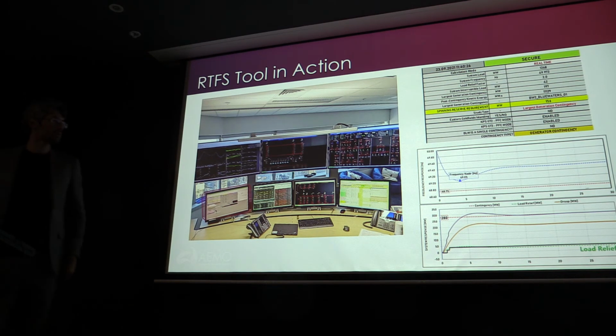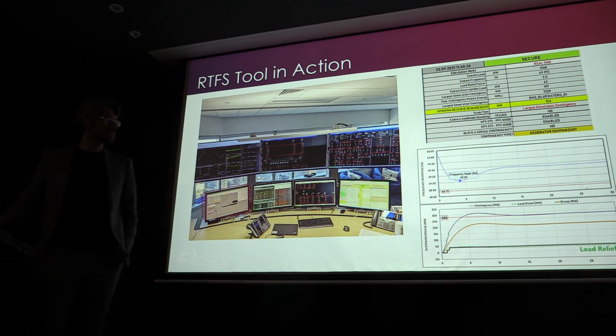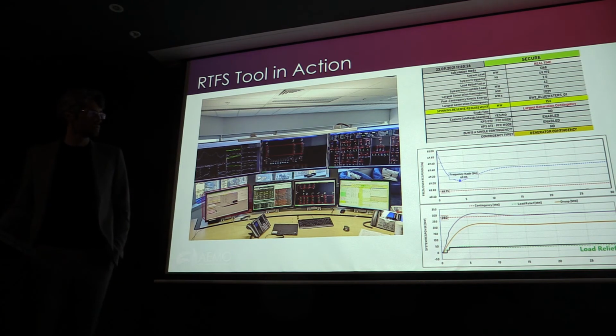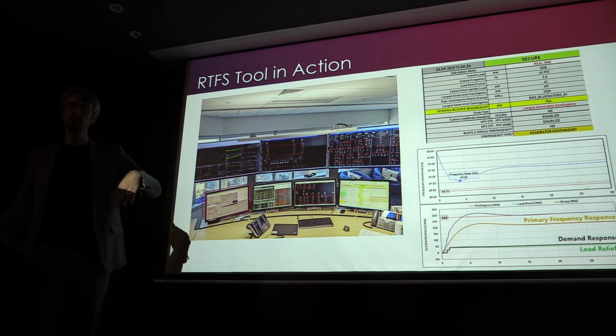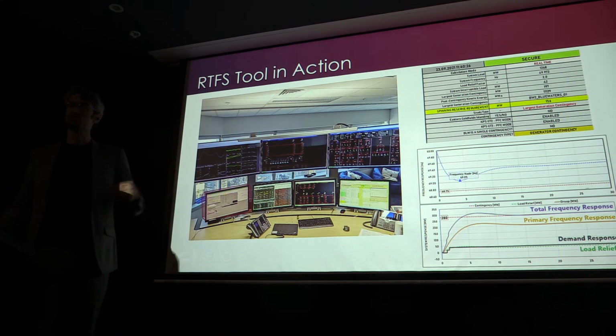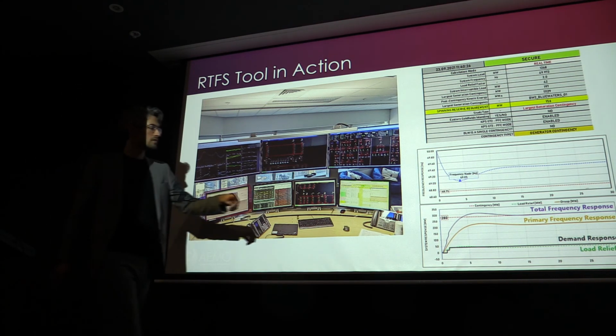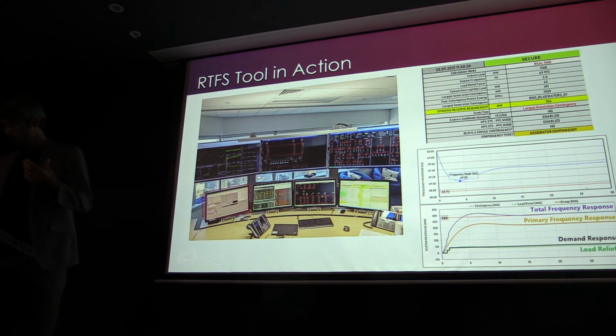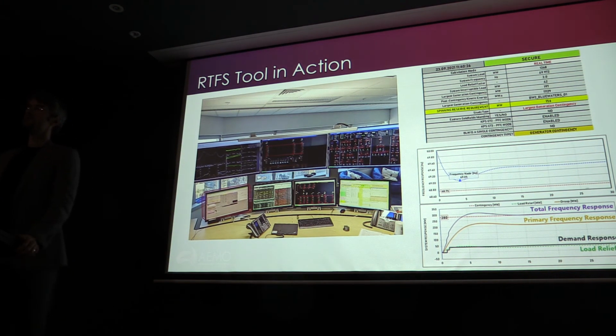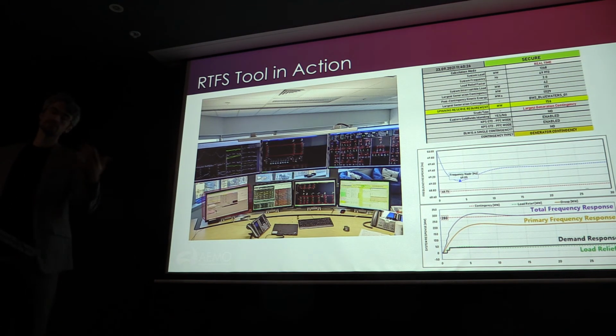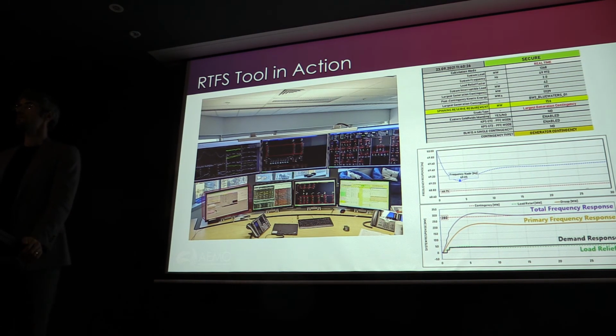Some components in it: the green dashed line is load relief, demand response or system interruptible load. We've got primary frequency response. All together, that would be total frequency response. The contingency size here is 280, so we have to provide exactly 280 to arrest the frequency or to reach a quasi-steady state condition.